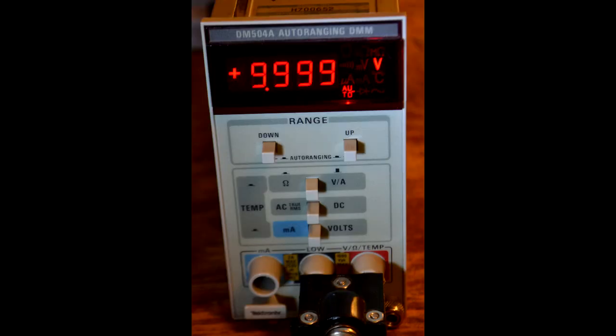The Tektronix DM504A is my favorite TM500 series digital multimeter. It has 4.5 digits precision, auto ranging, and simple front panel controls. Just 5 buttons to select between range, voltage and resistance, AC or DC, current or voltage, plus an option for temperature with a P6602 probe.